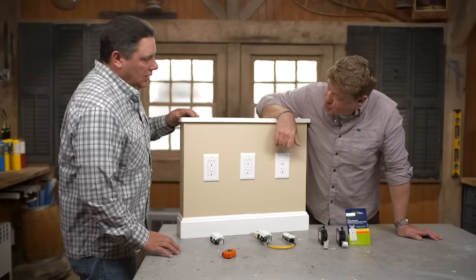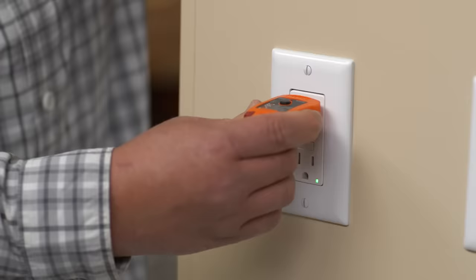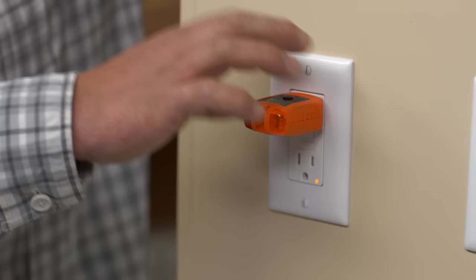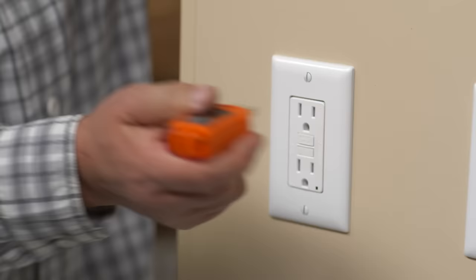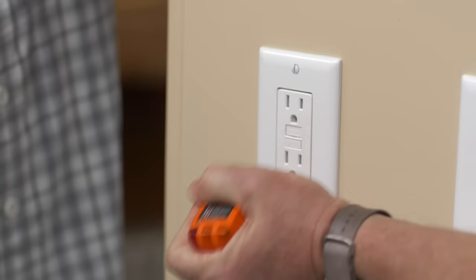I've seen them before, but tell us how we know we are GFCI protected. So the easiest way is we have one like this. You can see those test and reset buttons right in the middle. That's the easiest indicator. And this particular one has an actual green light to tell you that it's on. We can plug this tester in to show you that it's actually working — because this lights up right there. To verify that it's operating properly, we can press that button on the top. There's still power to the device, but nothing coming out. So when you plug something in, it's not going to work. Those buttons allow us to then put it back in place. Back on. And with it back on, we can now show that it's working. No problem at all.